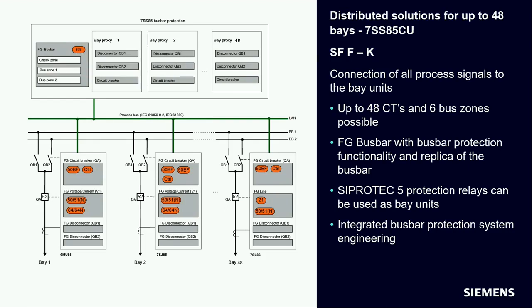In contrast, the 7SS85CU solution really lives up to its name, distributed busbar protection. Here you put all functionality like breaker failure protection, end fault protection, backup protection function in the merging units. You connect the graphical elements in the single line to its representatives in the merging unit. After completing the engineering of the merging units, you must update the central unit in the single line configuration. During this update operation, the system configuration created in the single line editor is also created in the 7SS85CU using the representations of the connected bays, circuit breakers, disconnectors, and measuring points.